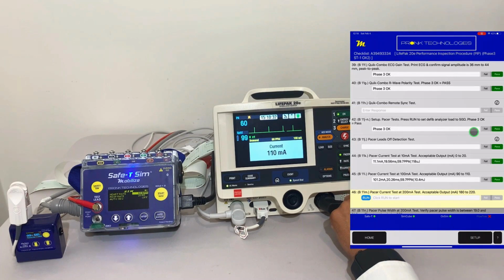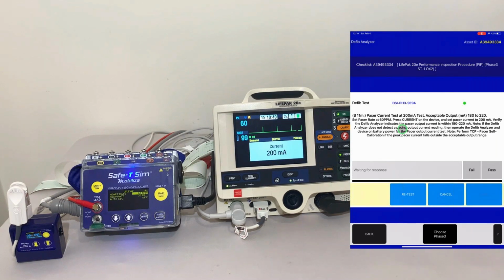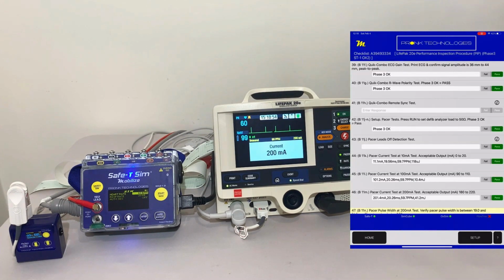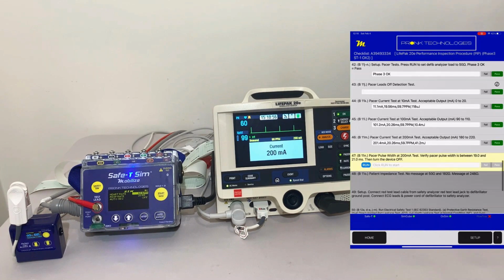One more, we'll do it at 200. It's important to make sure that these results are well within specifications, and if there's anything out or right on the edge, it's definitely important to repeat that testing a second time. So we have a target of 200, we have a result of 201.4, well within the range we have specified here. This test passes. The next test is we want to do a pulse width test.